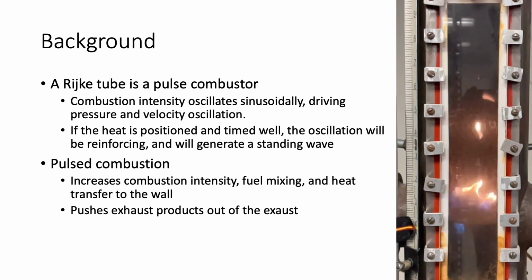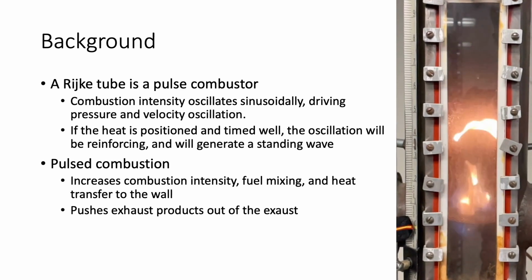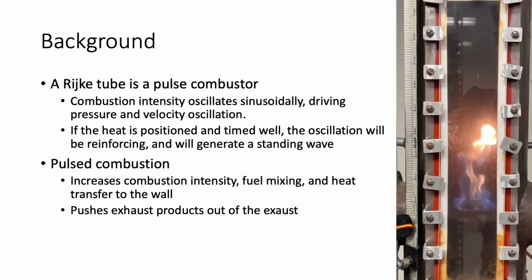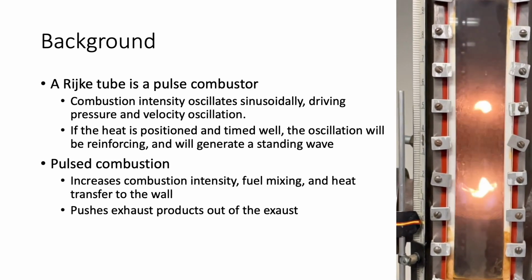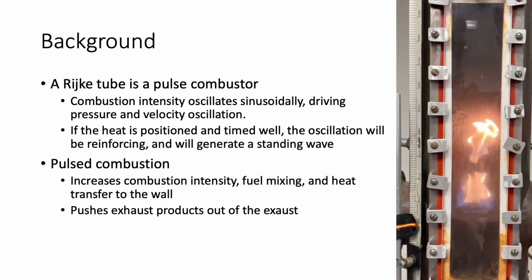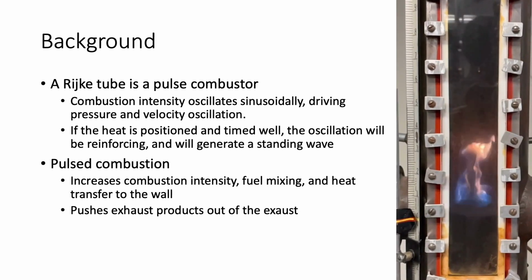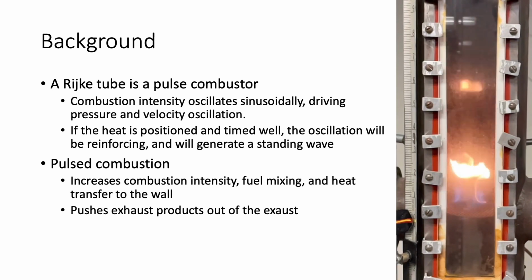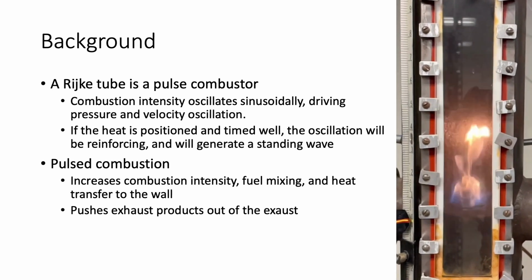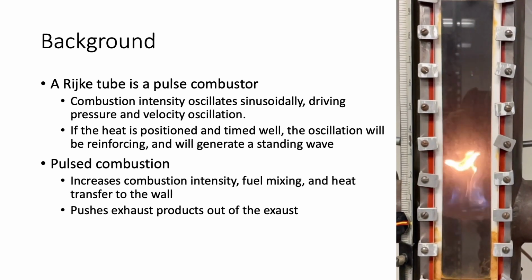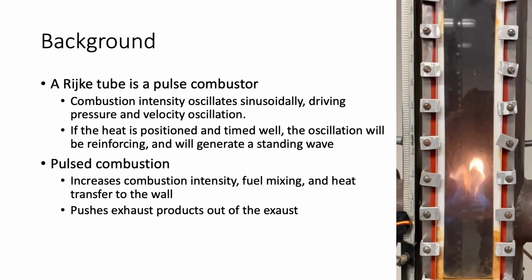In a pulse combustor, combustion intensity oscillates sinusoidally, like a sine wave, which drives pressure and velocity oscillations within the combustion. If the heat source is positioned correctly and the injection of fuel is timed correctly, then this oscillation will be self-reinforcing and will generate a standing wave. This is resonance. Pulse combustion has many interesting properties.